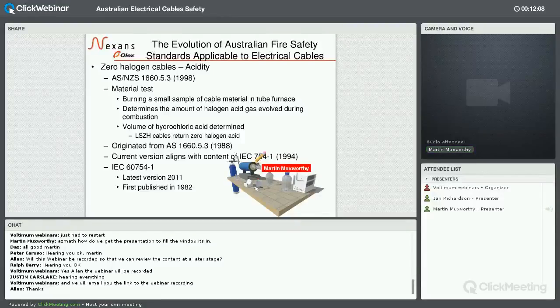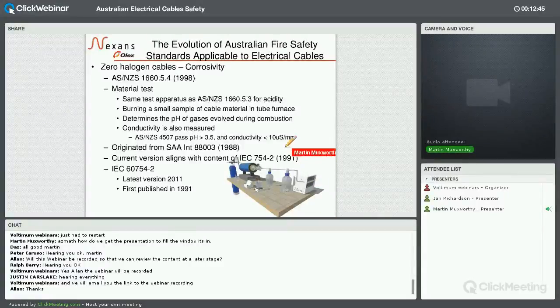And what really happens is there's a number of ways it can be done, but one example is air is pushed down the enclosed space, and what you do is you drive the smoke and the air through a number of bottles of water, and so what happens is any particles and residue in that smoke gets collected in the water, and from there you can measure the acidity content. In the next slide you'll see that not only can you measure the halogen acid content, you can also measure things like the pH of the water, so this will tell you the degree of acidity, and you can also measure the conductivity of the water.